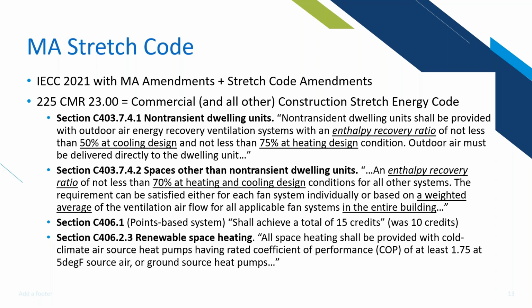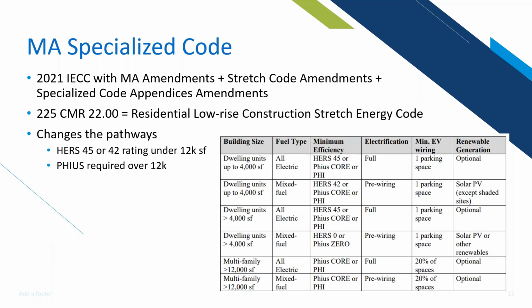So a couple more amendments worth noting, just because they have to do with the equipment that we sell. There's a points-based system in C406.1 where you used to be able to get away with 10 credits, but now you need 15 credits. And the easiest way to achieve those 15 credits is actually using renewable space heating. You get all 15 credits if you use an air source or water source heat pump that can give you a coefficient of performance, or COP, of at least 1.75 at 5-degree ambient source air. Okay. So that's stretch code.